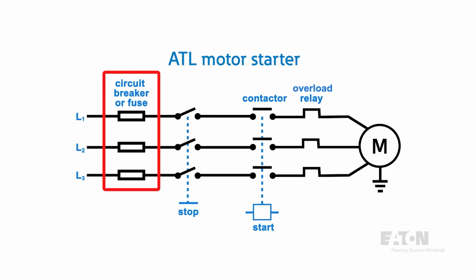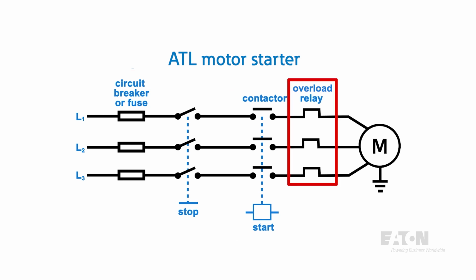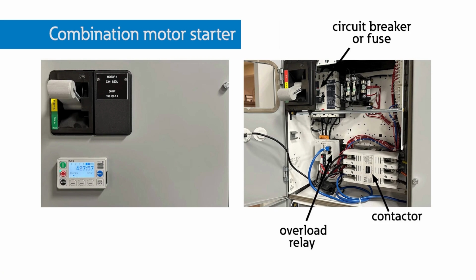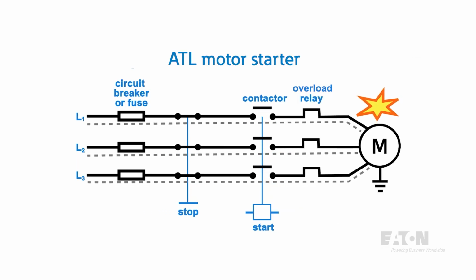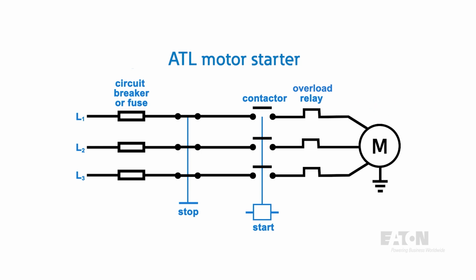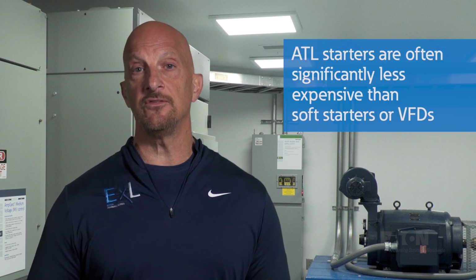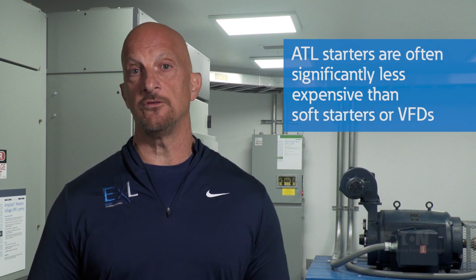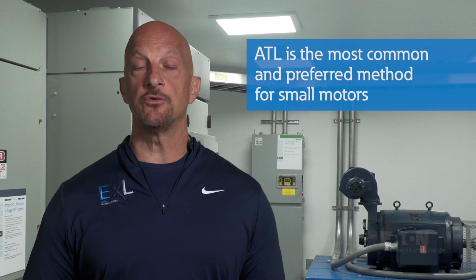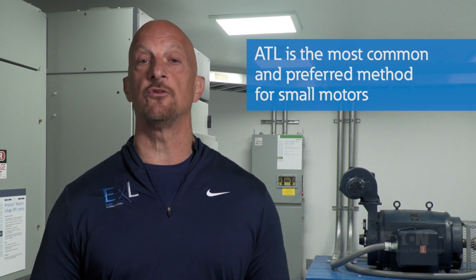The ATL motor starter has to work with a fuse or breaker to trip during fault conditions. This pairing of a motor contactor, overload, and a fault protection device is often called a combination motor starter. To turn off the motor, you trip the contactor via a switch or other control method. Depending on the overload relay and protective device associated with the ATL starter, it is often significantly less expensive than the other 2 methods of motor starting. Therefore, it's the most common method and usually the preferred method for small motors. With larger motors, 25 horsepower or larger for example, soft starters or VFDs are typically standard practice.